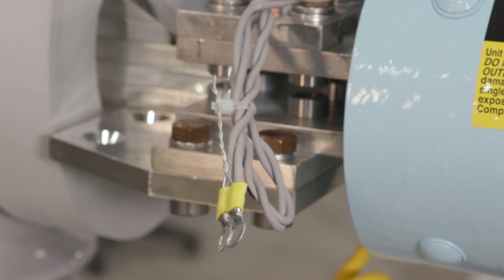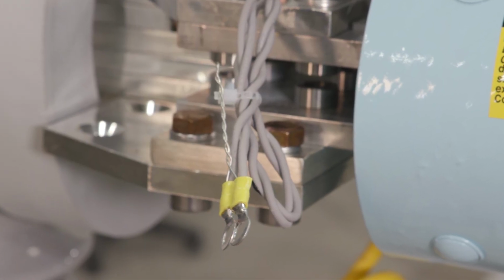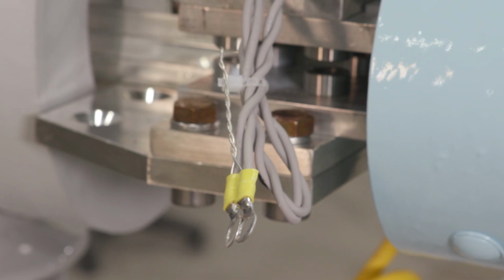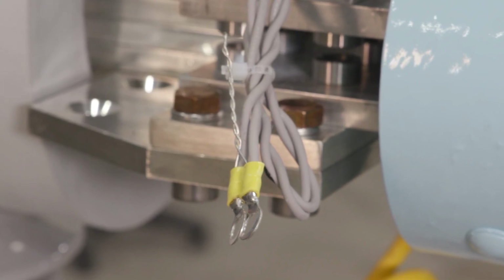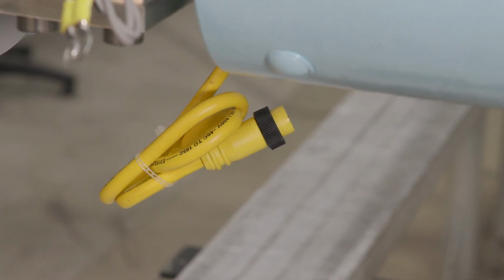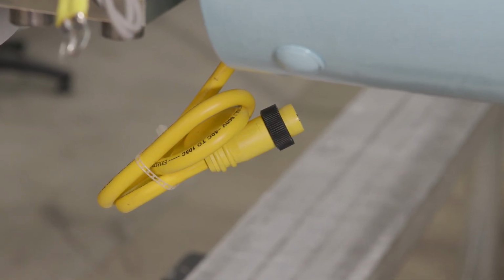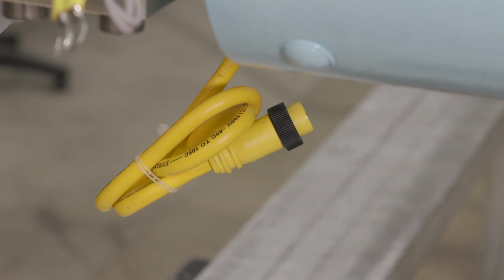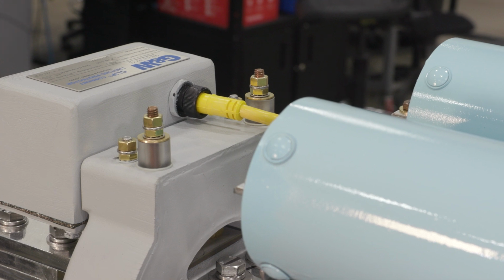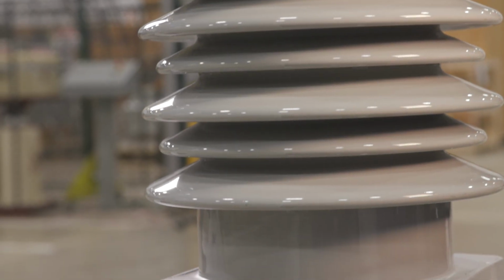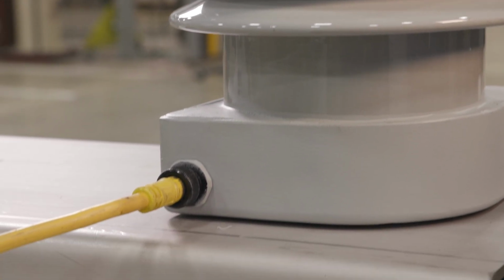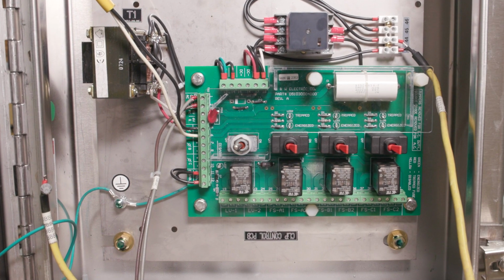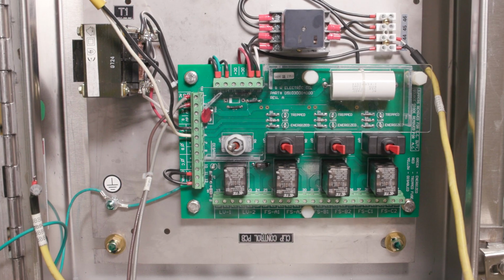To ensure the two gray firing leads on each interrupter are not connected to the SFL, they should be shorted, tightly twisted, and secured parallel to the interrupter body. Now confirm the yellow remote indication cable from the interrupter to the isolation transformer, or IT, is not connected and is pulled back and restrained. The yellow cable from the SFL to the IT is connected. The yellow 30-foot cable from the base of the IT to the control box is connected. And finally, the control box is grounded with continuity to the base of the IT.